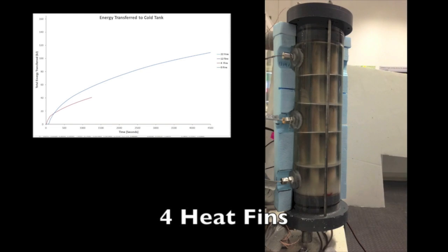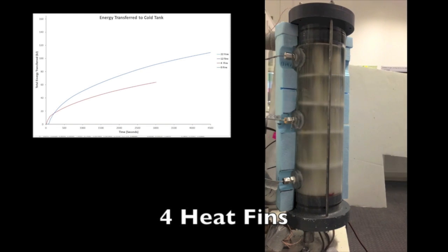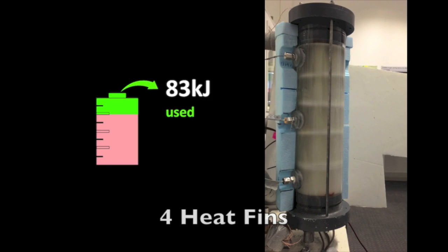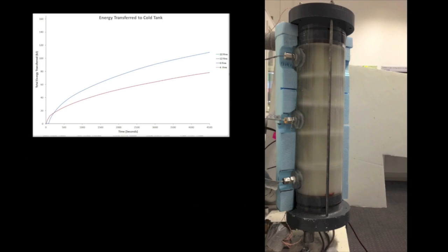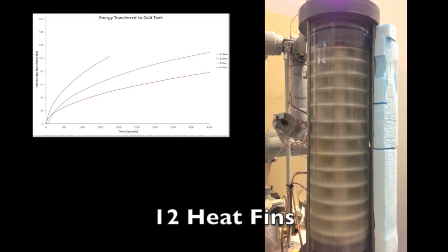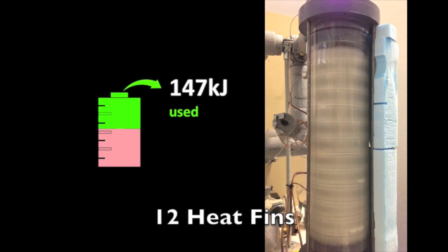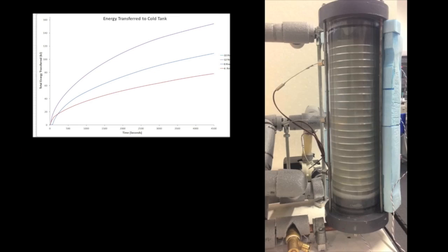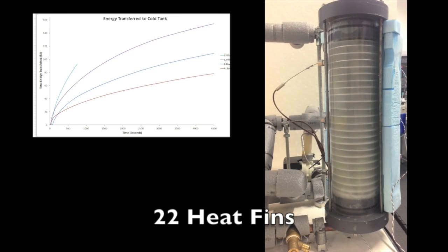Transfer fins were installed to increase the surface area, which at first, due to build-up of paraffin between the fin and the pipe, had a negative effect. The number of fins was increased to give a 20mm gap between each fin, allowing the paraffin to solidify in layers. The fin gap was then decreased to 10mm, which produced over 1 litre of hot water at a rate equivalent to a shower at 8 litres per minute.